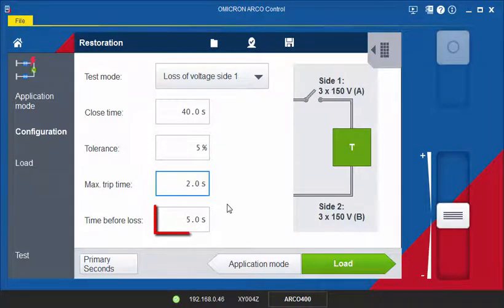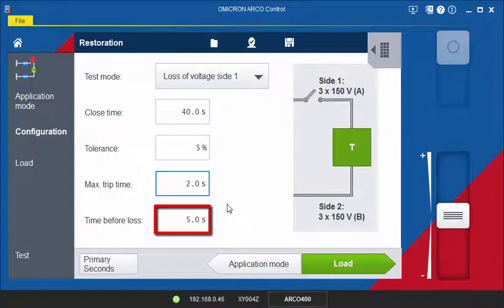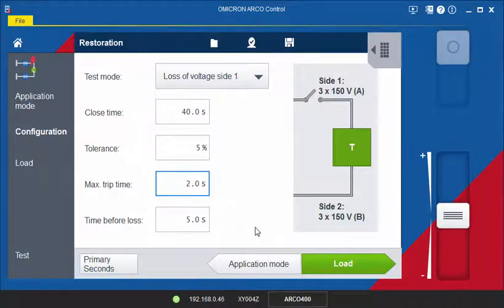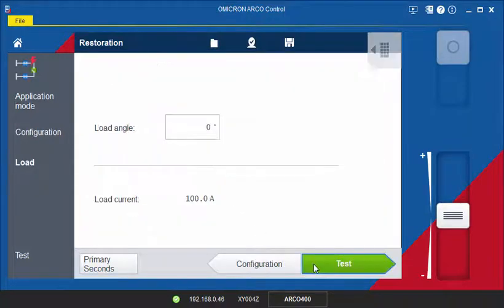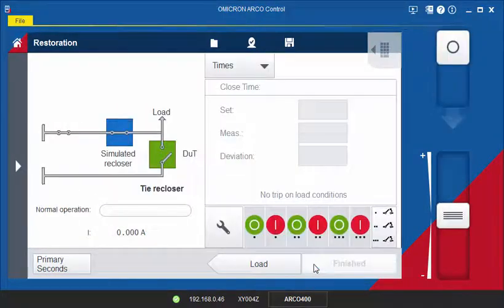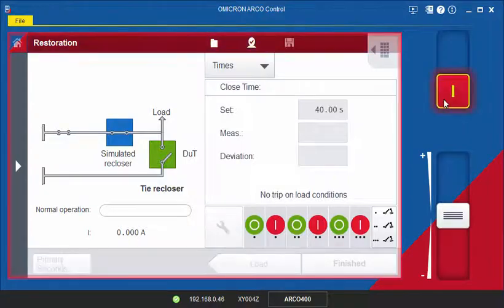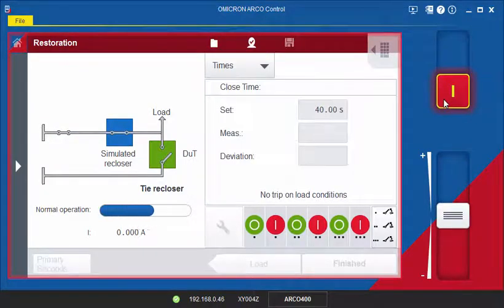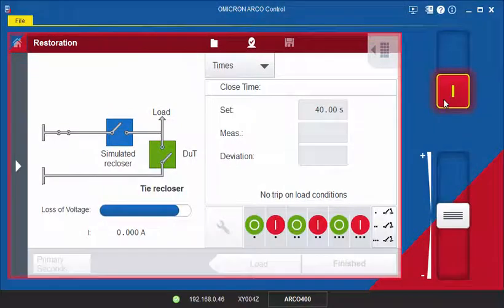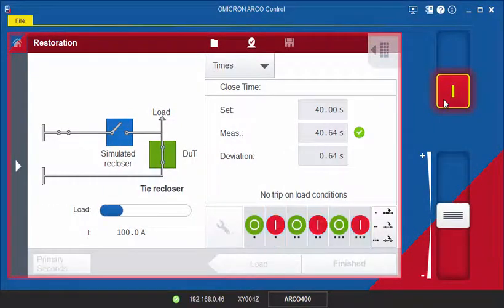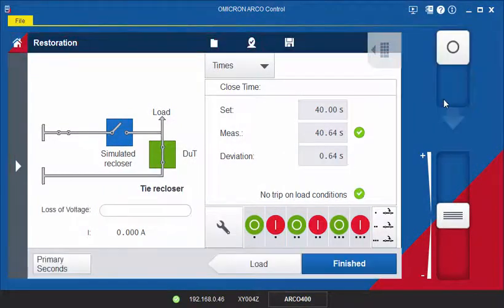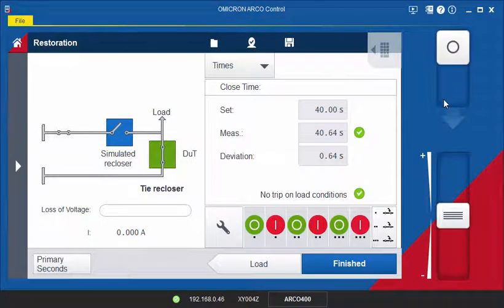During the time before loss, the load current will be output as a pre-fault state. When you have entered the load angle on the next page, you can start testing. The test will be assessed OK if the measured close time is within the defined tolerance and the recloser control did not trip during the pre-fault state.